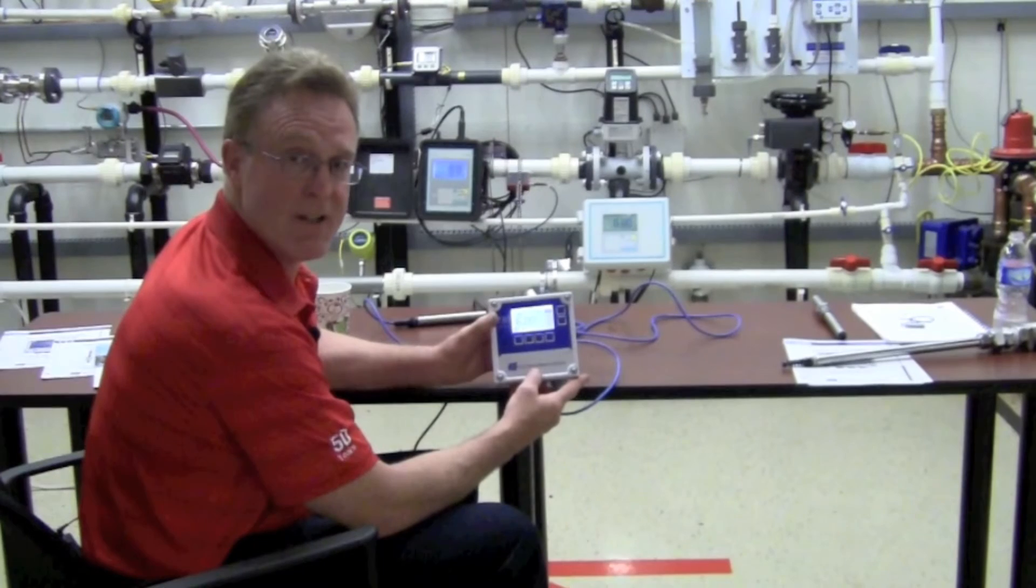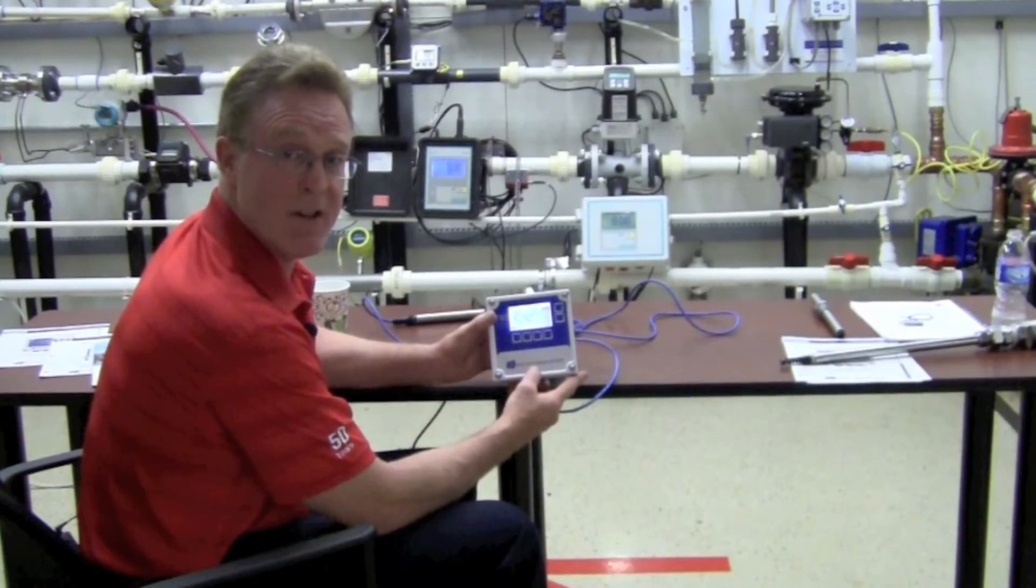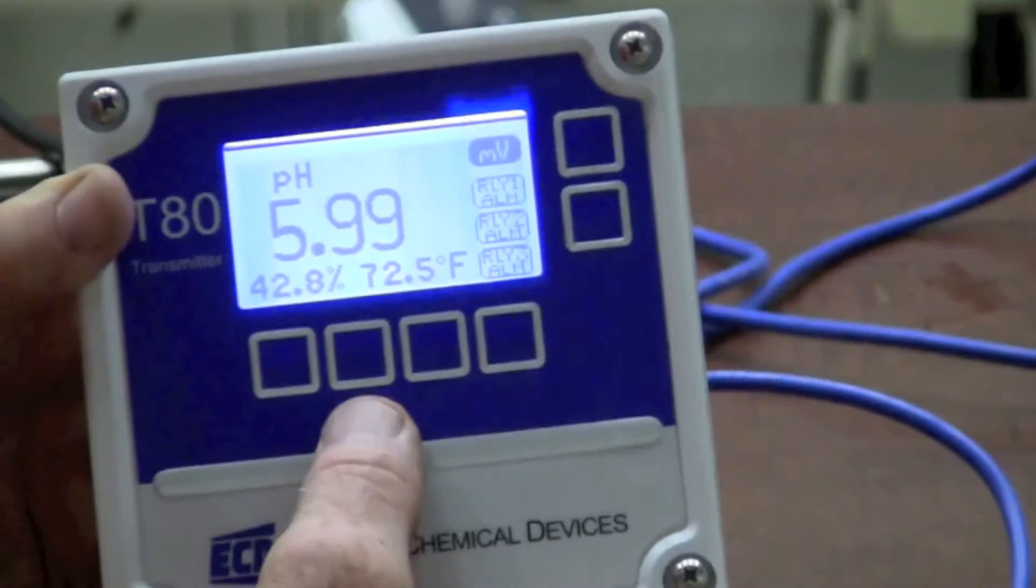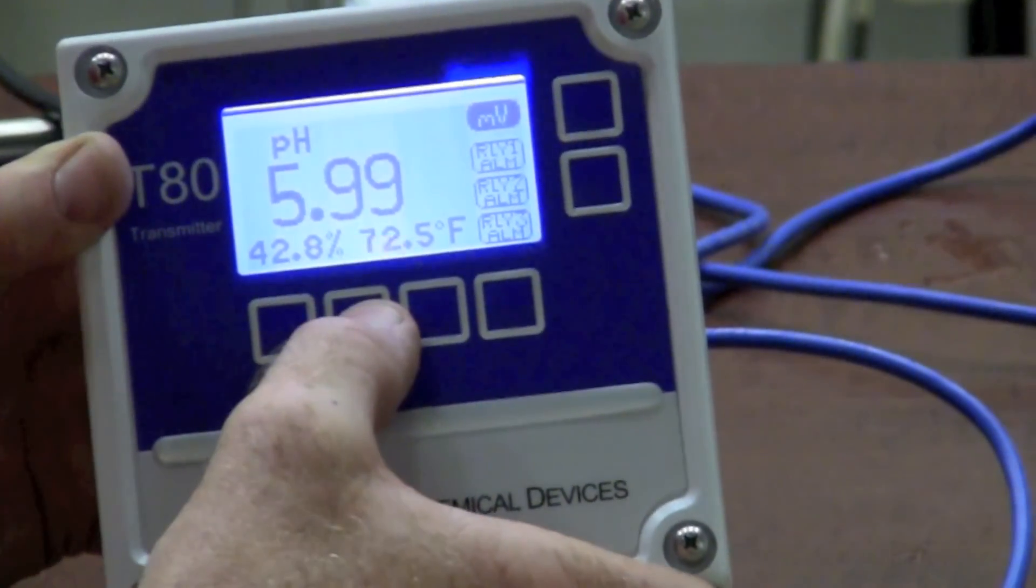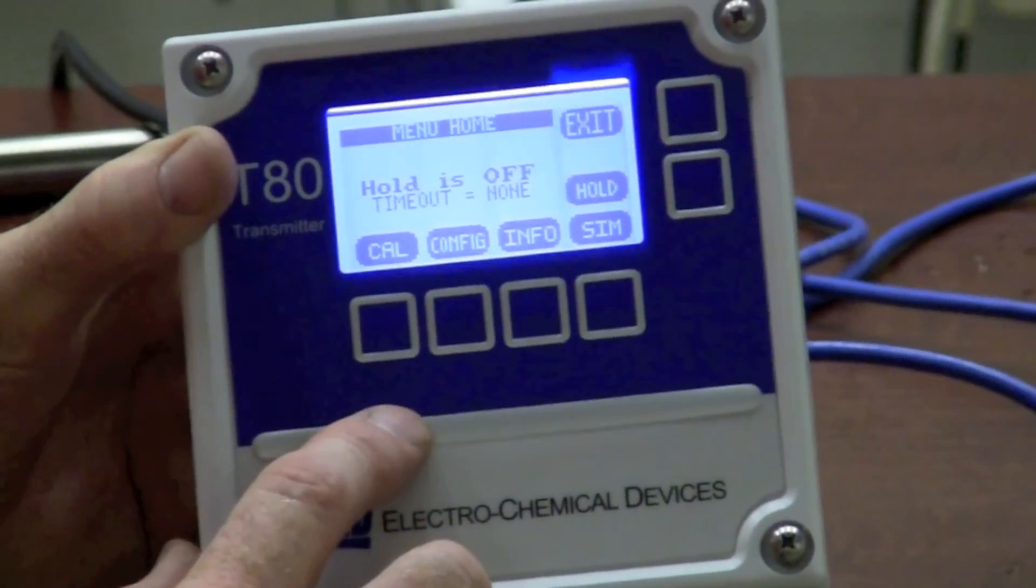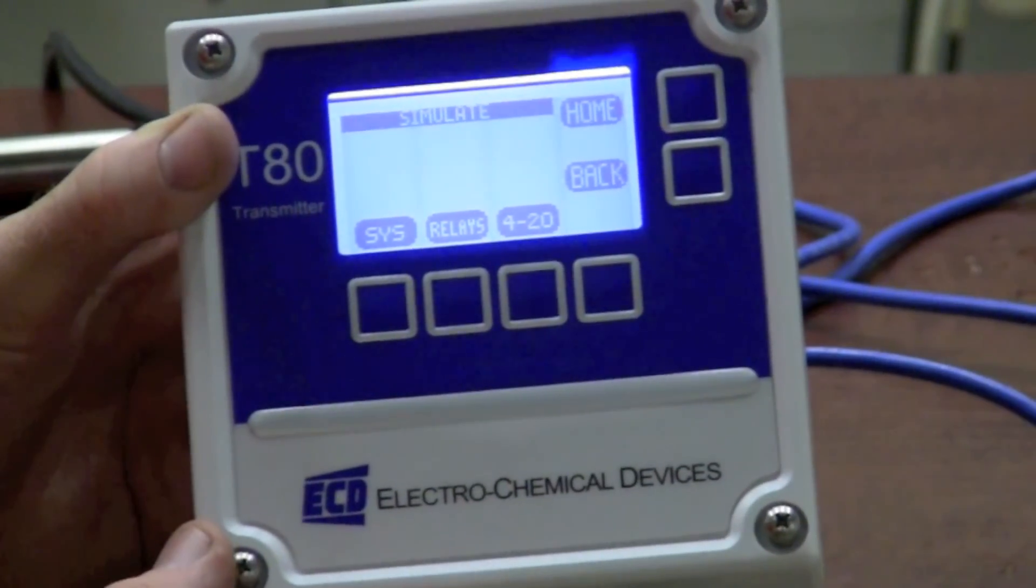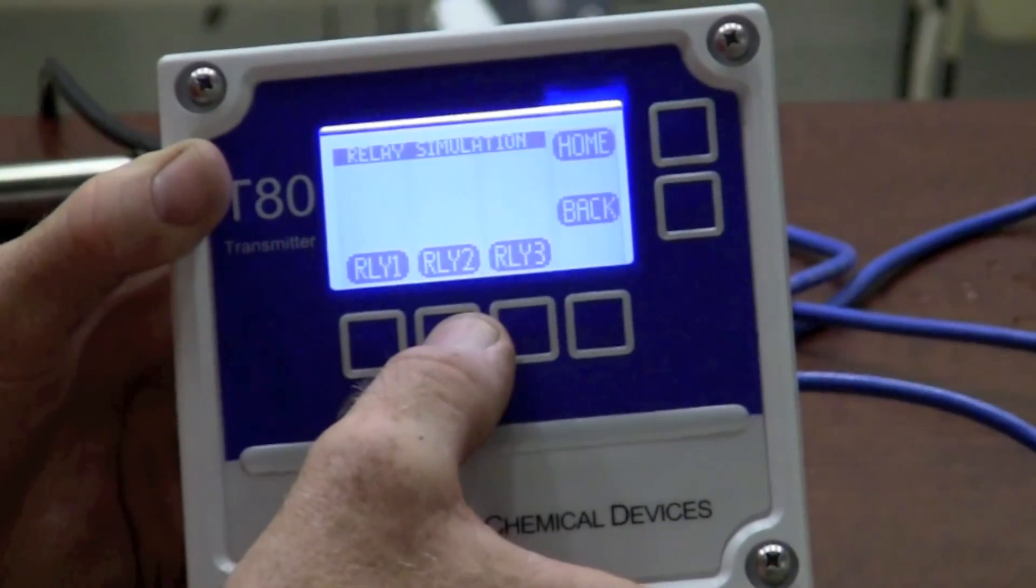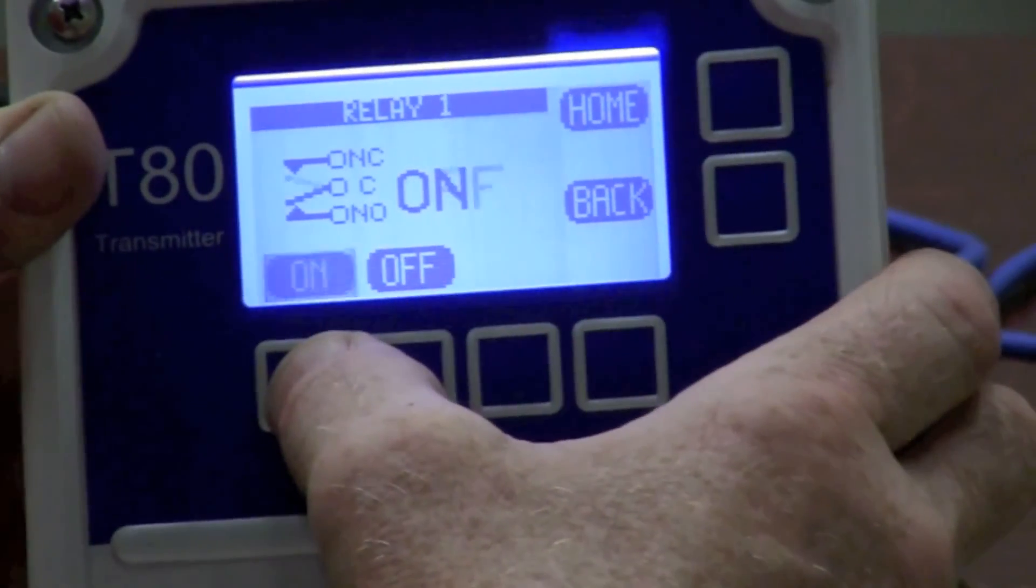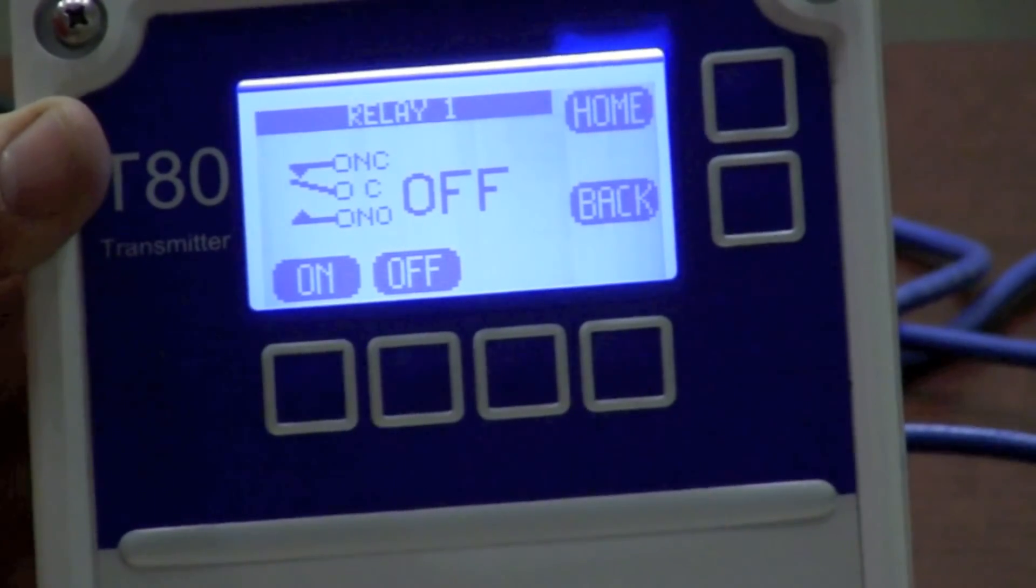Now that we've completed a calibration, I want to show you a couple nice features of the S80 slash T80 combo to make it a true winner. On the display, with the soft keys, once again, I'm going to hit any one of the four twice in succession. And instead of going into the calibration, I'm going to go into the simulate. With simulate, this allows me to fire my relays if I wish. Relay one, two, or three, and force it. This way, I can ensure that my chemical feed is going to activate as I expect it to.